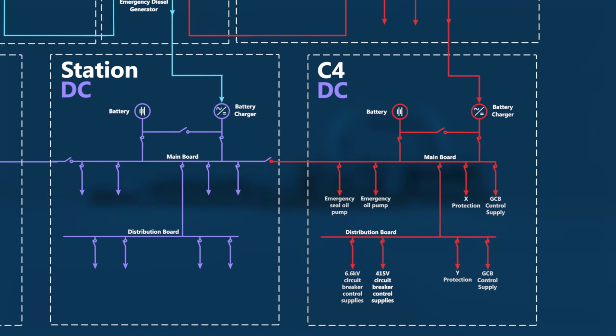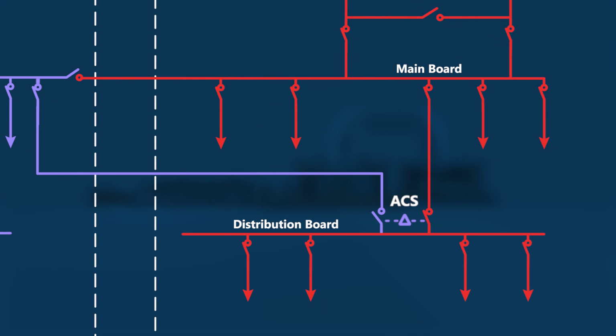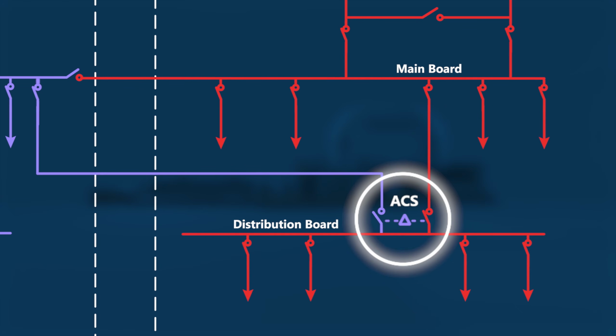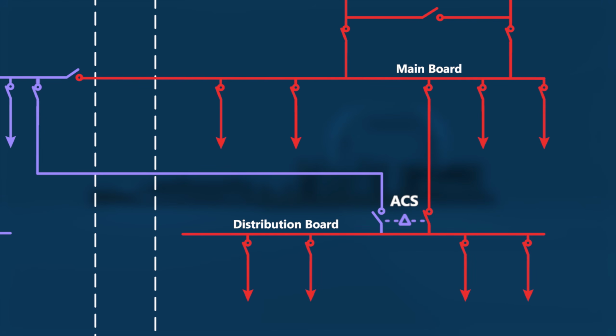There is also a mechanism in the C4 DC system that automatically responds to a loss of supply. This is called the Automatic Changeover Switch, or ACS. The ACS sits between the main board and distribution board and monitors the DC voltage in the main board. If this voltage falls below the required level, the ACS automatically changes over to supply the distribution board from station. However, the automatic switching capability of the C4 ACS had been damaged in a previous incident, and it could only be operated manually. In this state, the ACS had no way to automatically reroute power from station to the C4 distribution board.